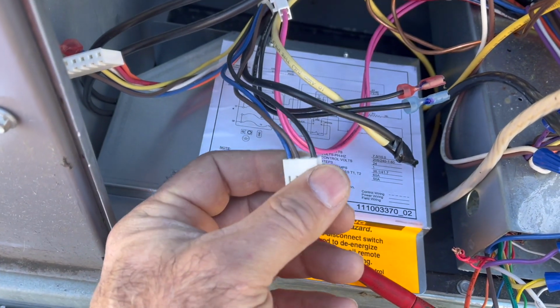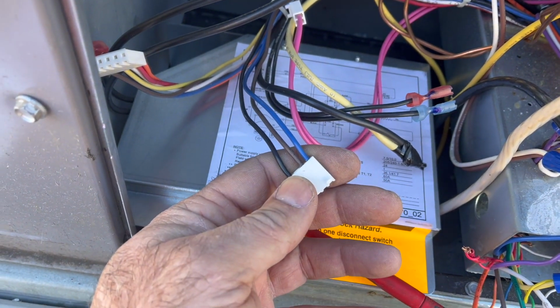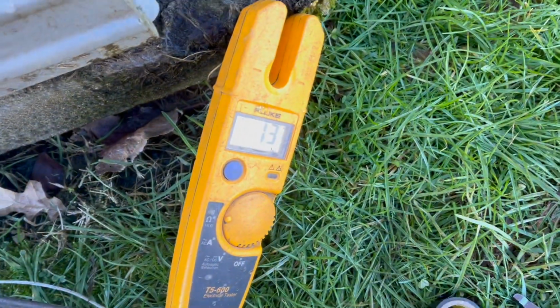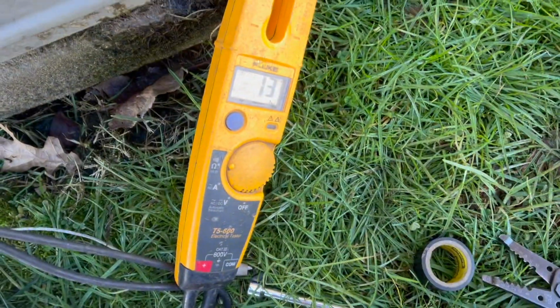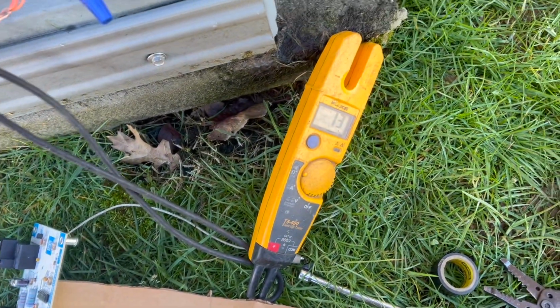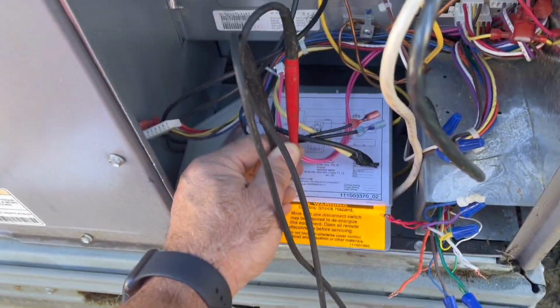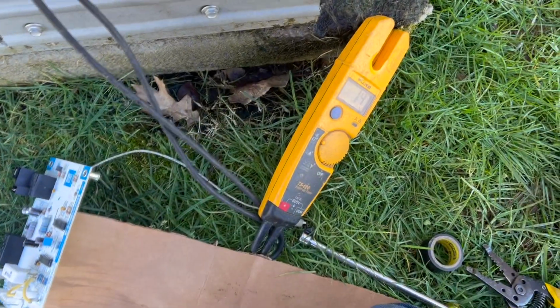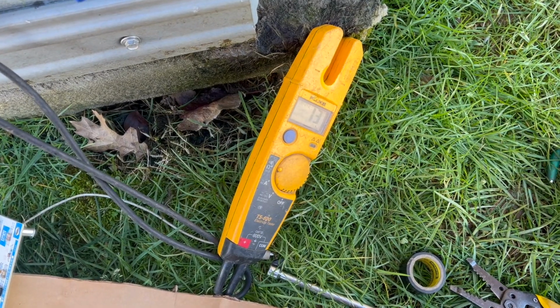Let's see, that plugs on this way. So it's going to be from black to brown is going to be the reversing valve coil. And she is 13 ohms, so that should be good. So we just need a defrost board and we should be back in business, along with maybe a used thermostat.